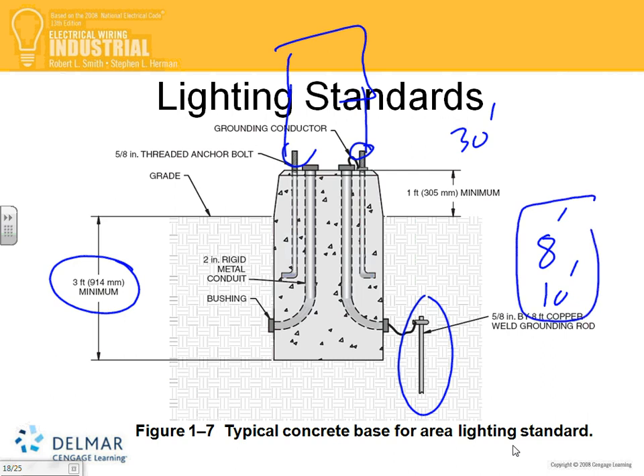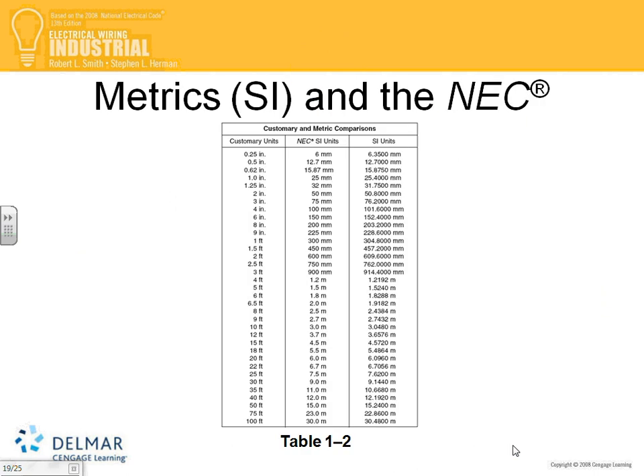And sometimes they go every other one, every other pole. You take the first one, you ground it. And again, this is a grounding rod, guys. The only reason for this rod is lightning. It's nothing to do with grounding. Do I need to tie this grounding rod, guys, to the grounding system of my building when I bring the circuit? Yes. But this is mostly lightning.